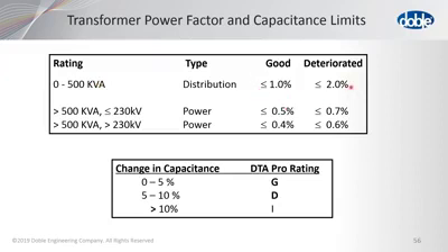And as you might expect, the power factor limits are fairly high on those. But when you get into power transformers, greater than 500 kVA and less than 230 kV, we have a more strict limit on the power factor. Remember, a lower power factor is better, right? So anything below 0.5 in those ratings would be given a good rating. Now, when we get to greater than 230 kV, we become even more strict, where we don't want you to go over 0.4 to get a good rating. Anything between 0.4 and 0.6 is deteriorated. Anything greater than 0.6 will get an investigate.